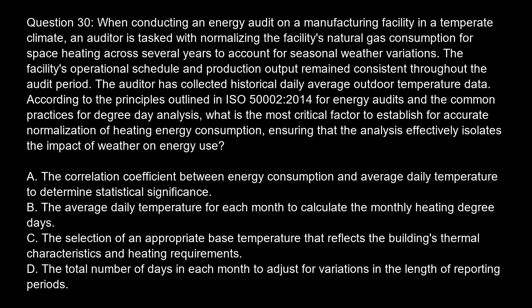The correct answer is C. The selection of an appropriate base temperature that reflects the building's thermal characteristics and heating requirements. Explanation. The fundamental principle behind degree day analysis in energy auditing, as per ISO 50002, 2014, is to normalize energy consumption data for variations in external weather conditions, primarily temperature.